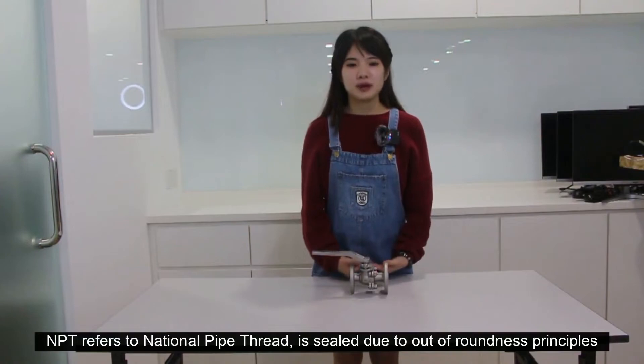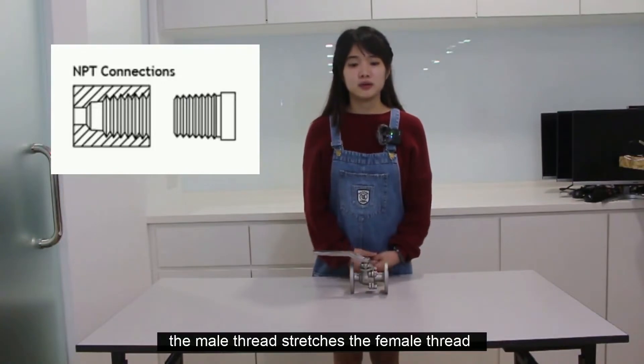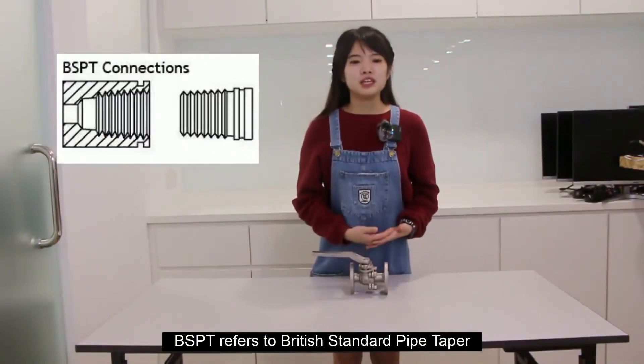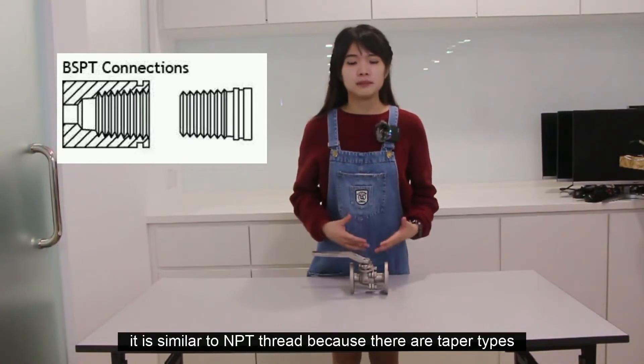NPT refers to National Pipe Taper threads. It works on the out-of-roundness principle, where the male thread stretches the female thread until there is a false-depth connection that can hold pressure on both sides. BSPT refers to British Standard Pipe Taper. It is similar to NPT because there are also taper threads.